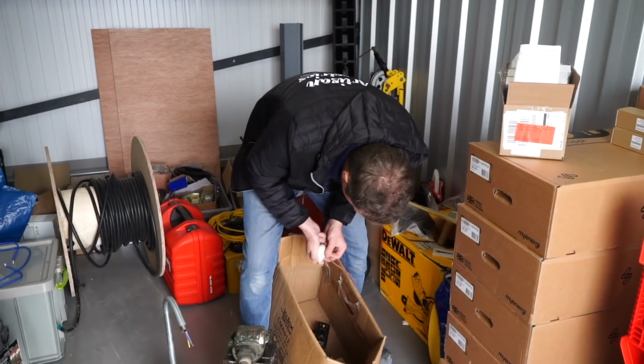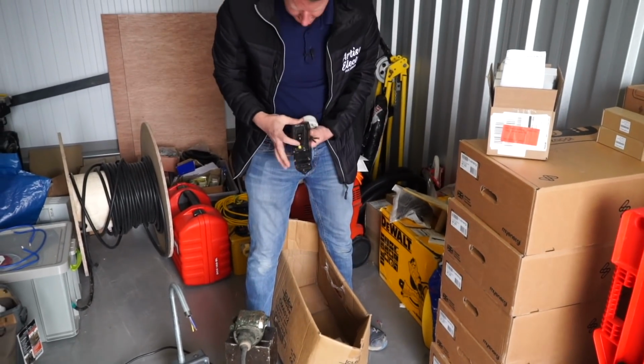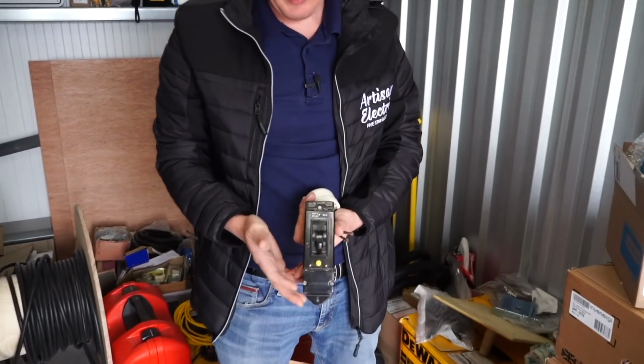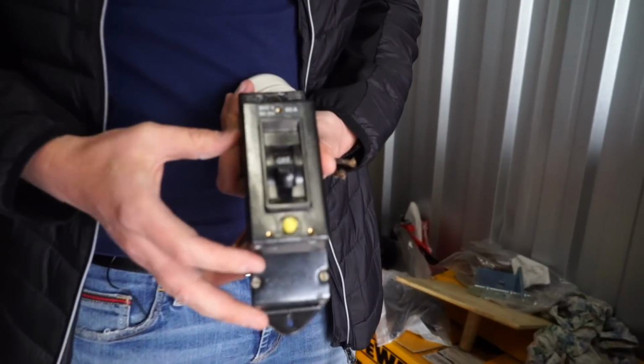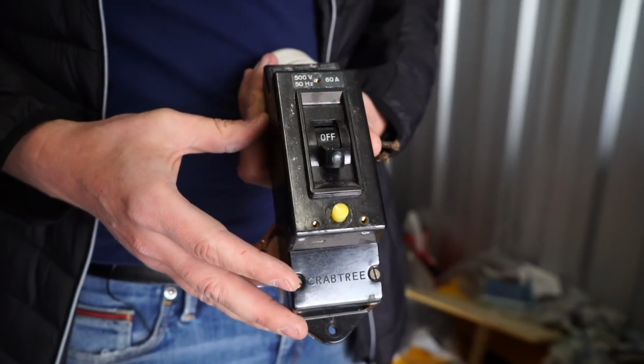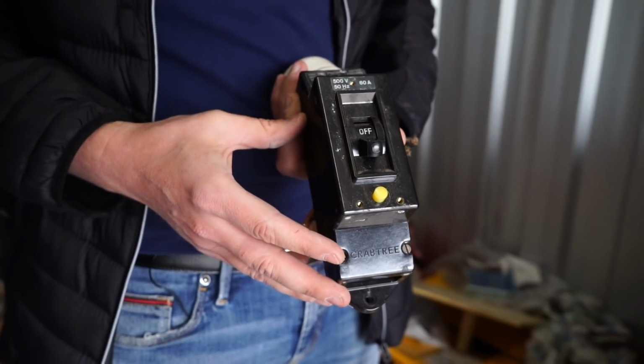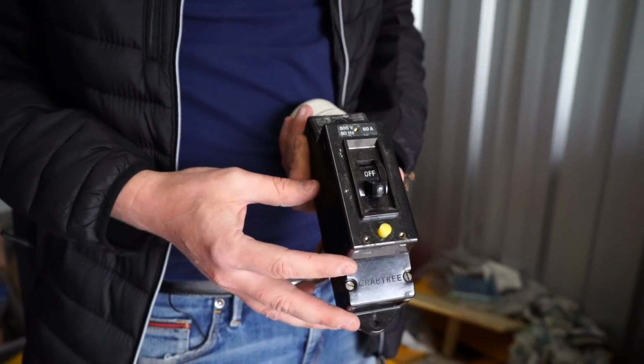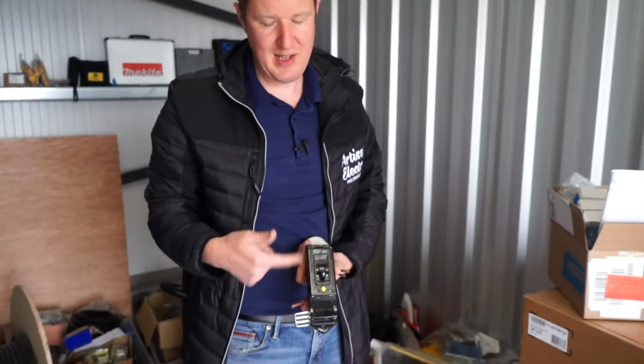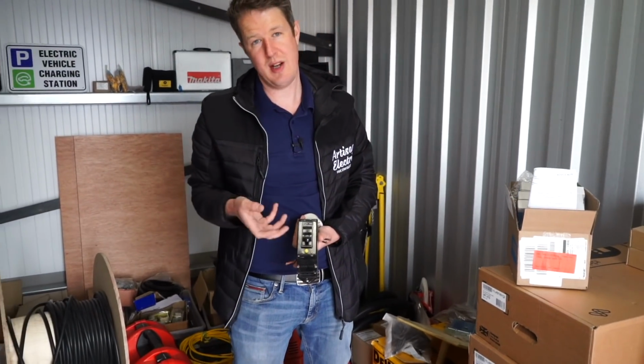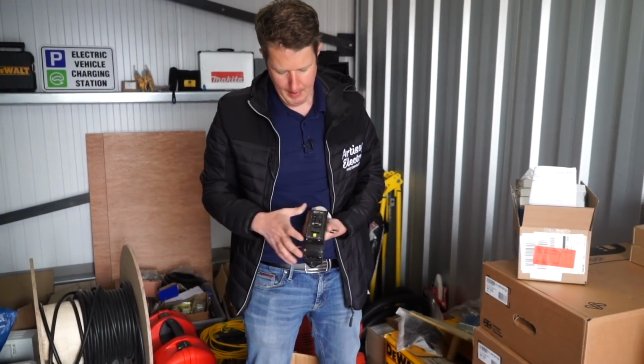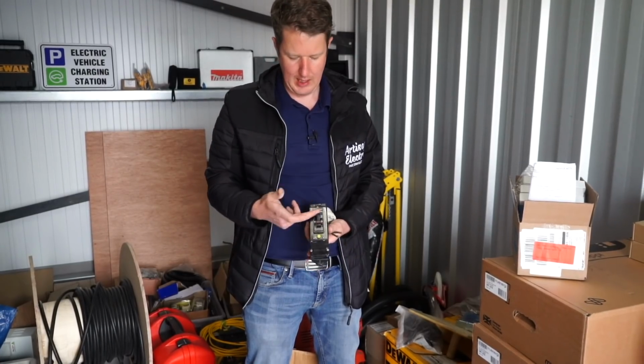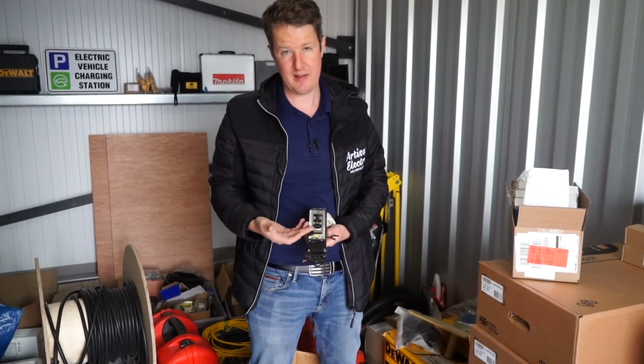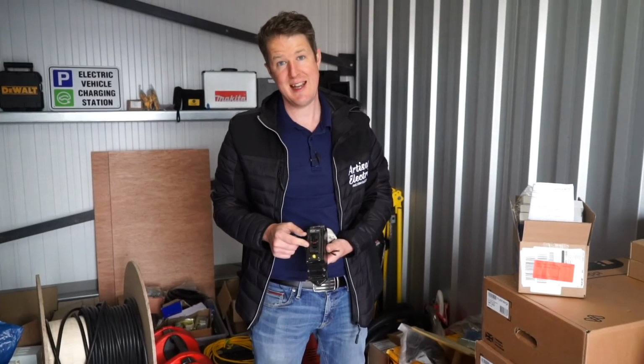What else is there? This is an old voltage operated RCD. Before the days of current operated RCDs, which trip at 30 milliamps of leakage current, this one measures based on voltage. I'm not really sure how it works exactly, but these are often found in old properties as a main RCD, especially if it's a TT system.